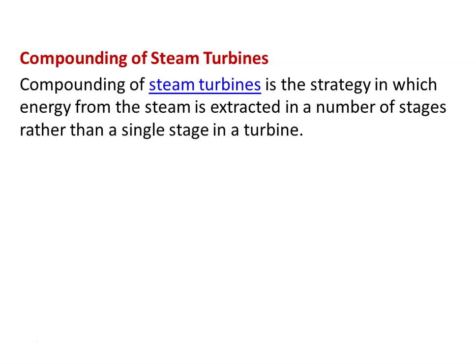In the previous lecture we discussed the single stage impulse turbine. The limitation or disadvantage of the single stage impulse turbine is that the exit velocity from the turbine is very high. To utilize the velocity of the steam effectively, we go for multiple stages — using the steam energy, the enthalpy, in more than one stage. This is called compounding of steam turbine. In a practical steam turbine, the number of stages will be around 30 to 40 depending on the power generation.